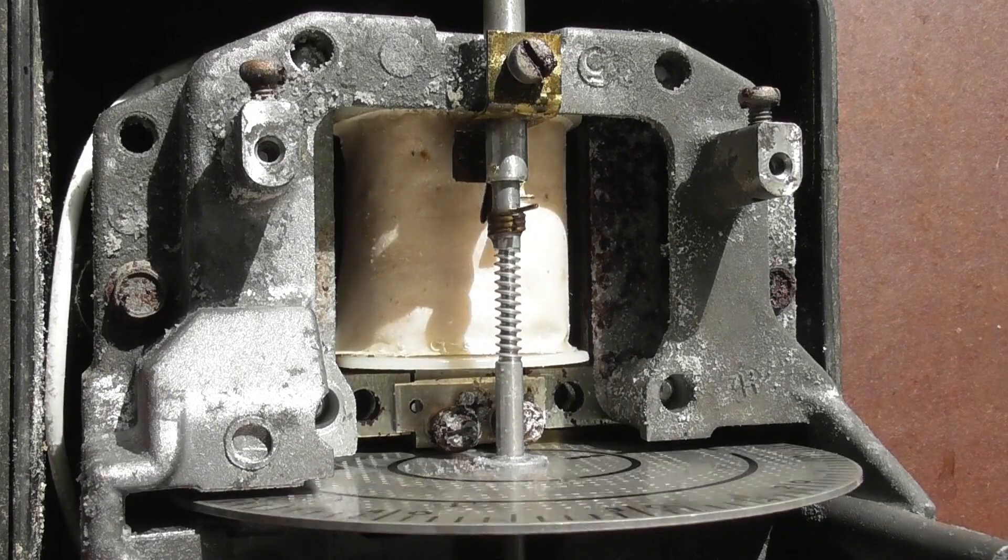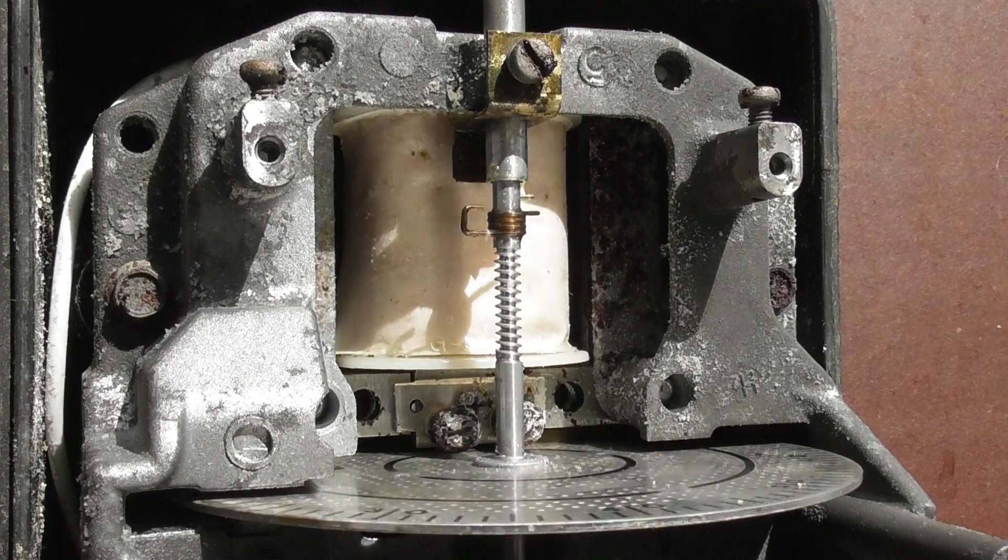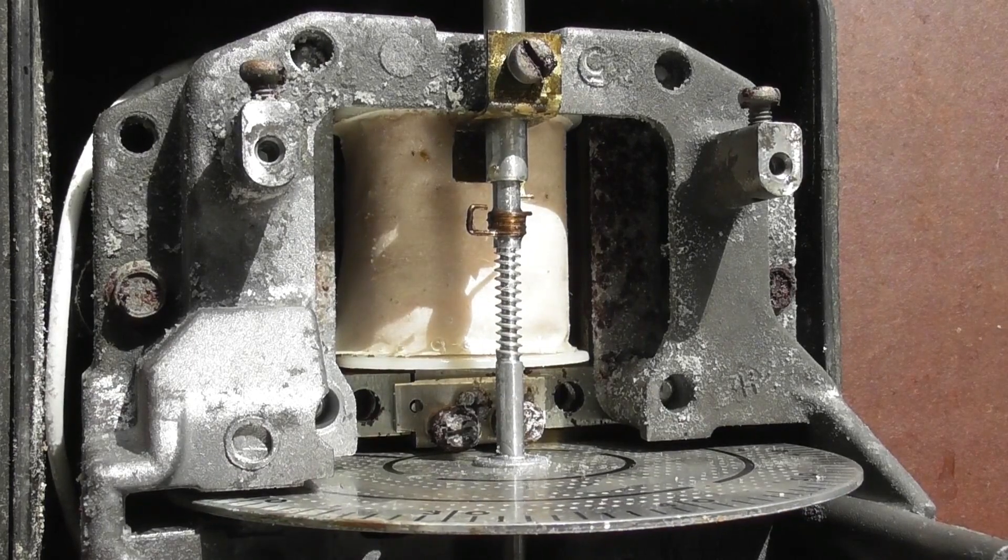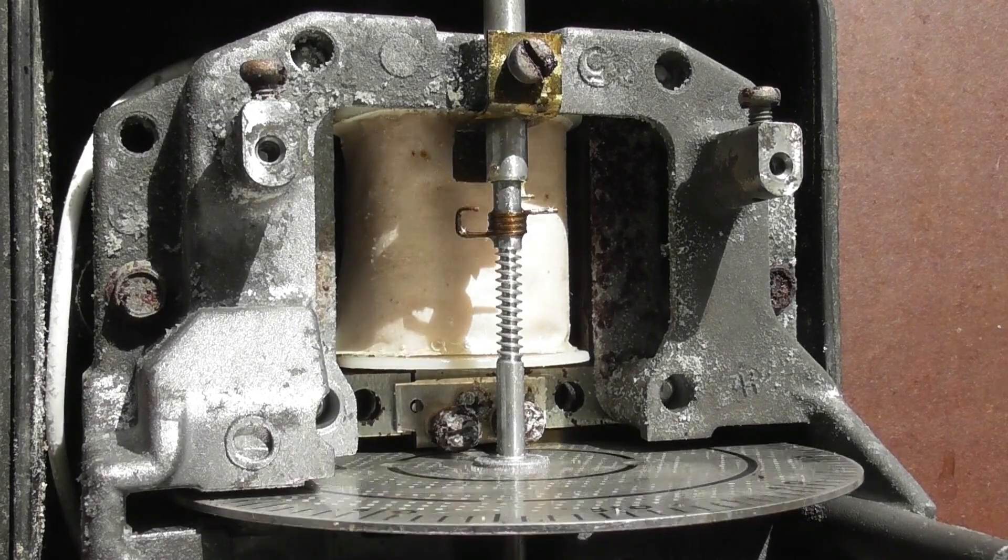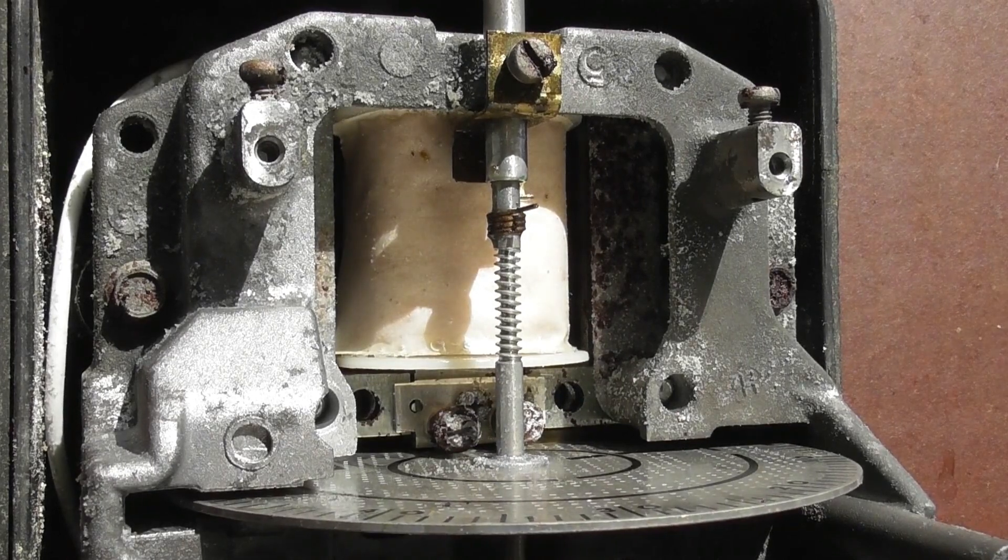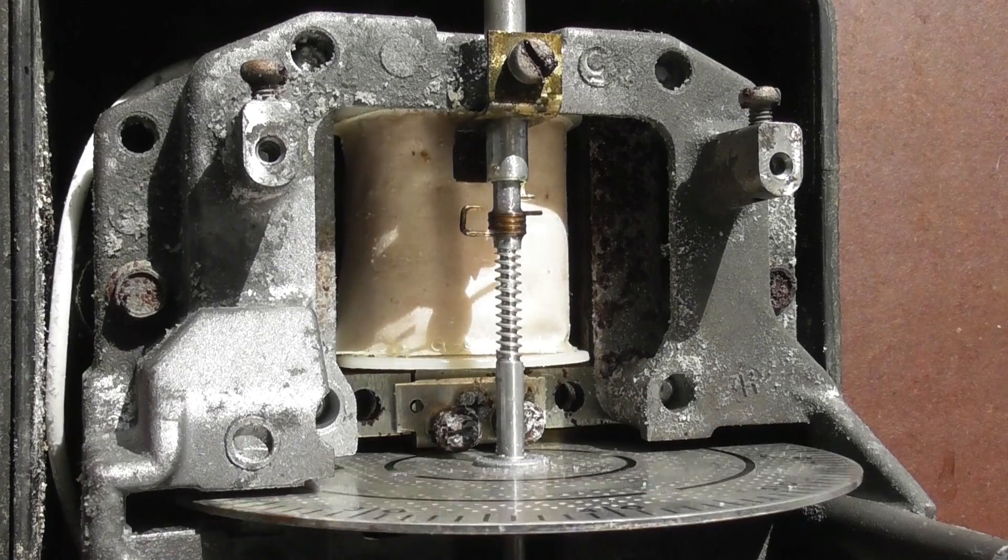Okay, I'm running forwards now in normal position, but say somebody decided to generate back into the grid or something went wrong. I'll swap the polarity and you'll see the meter will halt itself straight away. I'll put it back in the correct rotation, and the meter advances.